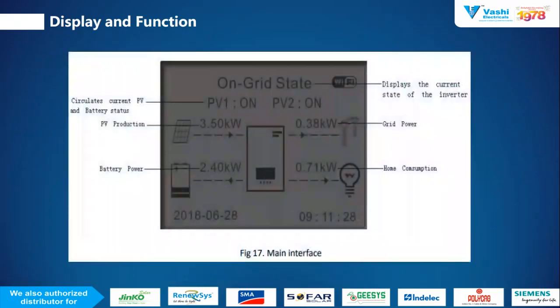So in the display, if the on grid or off grid LED is continuously blinking or flashing, it means it is in standby mode. You have to consider that some problem is there in the on grid or off grid whenever the LED is flashing in the particular mode, right? Here is the image of the display part, where on the left side is the PV production and battery power, and on the right side are the grid power and load consumption indications. On the top side of the display there are PV1 and PV2 voltage, continuously changing with the different parameters. It will continuously circulate through PV1, PV2 and the battery system.